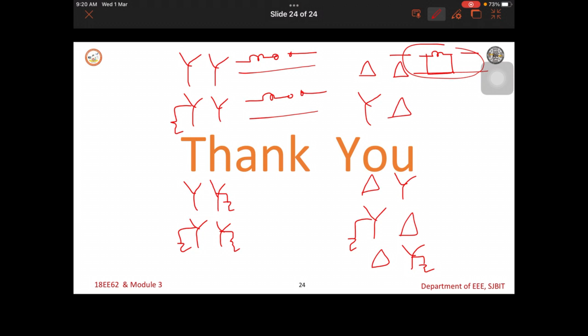So, I will just write how to write the zero sequence network like this, here zero sequence network like this, here delta means open, here you can write like this, this is a zero sequence network. Here you can write this is the zero sequence network, here is also zero sequence network like this, because here neutral current can flow in both the primary and secondary. And here is also delta. This is how zero sequence current can flow in the one phase. See here zero sequence current flows in the phases. Similarly, here neutral current flows. So, this is how we can write the zero sequence network for various combinations of the transformer windings. So, with this I will be ending this video.